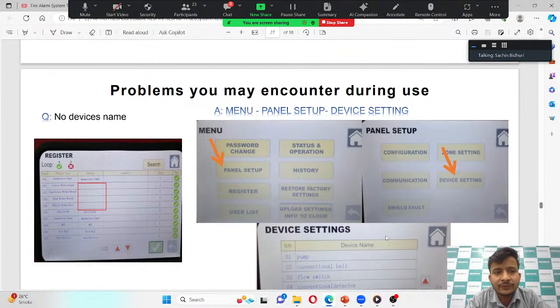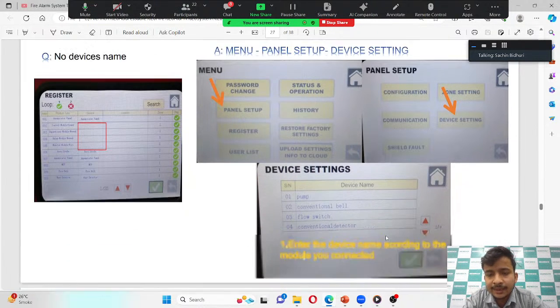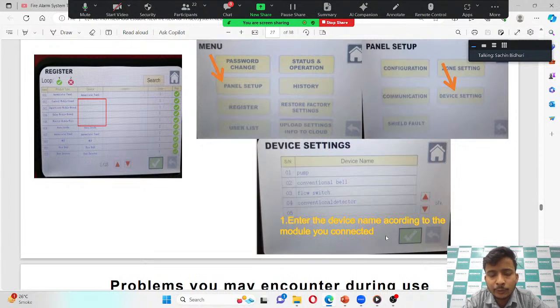Then no device's name. Sometimes the panel will not show the device's name, like for a control module. Sometimes it will define the product type and code also, but it will not give the name. So what you need to do is go to panel setup, then device settings, then device name, and here you can enter the device name whatever you want, and just click the save button.